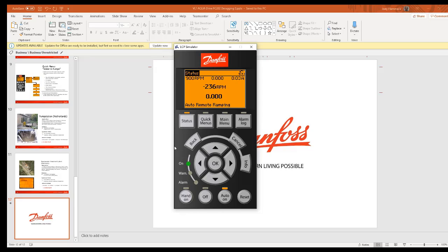Joey, does it have to be in manual mode or auto mode or hand mode to go into DERAG? It doesn't work in hand mode. It has to be in auto mode. If I come up and press hand, I want to run right now. It doesn't do the DERAG in hand. Got it. It is an auto mode only function.